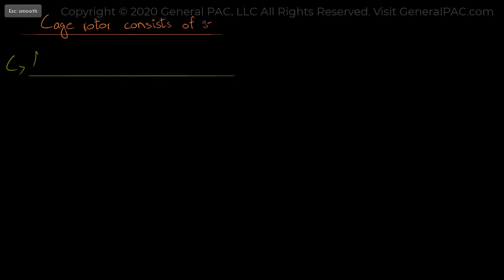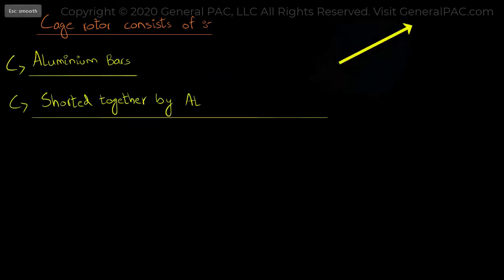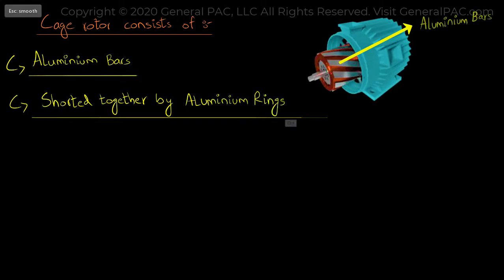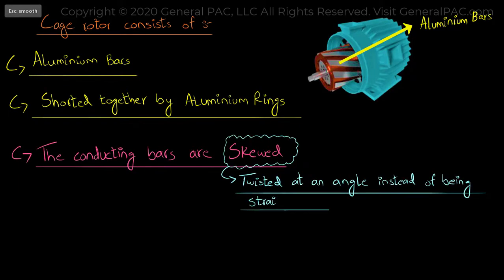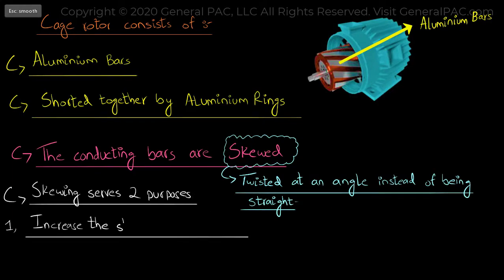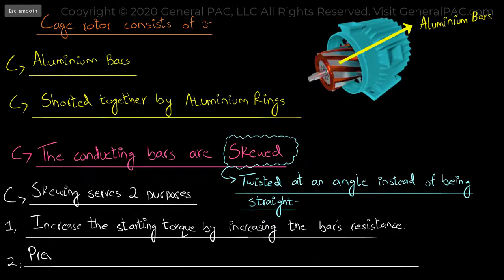Now a cage rotor consists of aluminum bars which are shorted together at both ends by aluminum rings so that the induced current may flow through them. Second, these conducting bars are generally skewed and they are twisted at an angle instead of being straight. The skewing serves two purposes: to increase the starting torque by increasing the bar resistance and to prevent the magnetic locking of rotors or else the motor will not start.